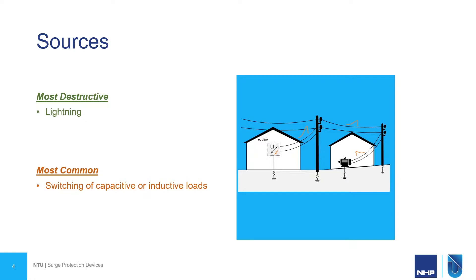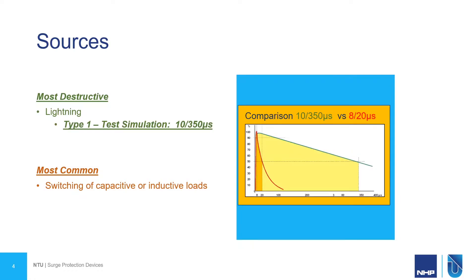Now no two surge events are going to be exactly identical. Each surge is going to differ in magnitude and duration. However, so that we can test and compare different SPDs, we need to simulate these events. So in IEC 61643, a lightning event is classed as a Type 1 and that is simulated by a 10 over 350 microsecond waveform, whereas the more common inductive type surge is a Type 2 and that's simulated by an 8 over 20 microsecond waveform. Note that the Type 1 has a lot longer duration, therefore it has a lot higher energy.